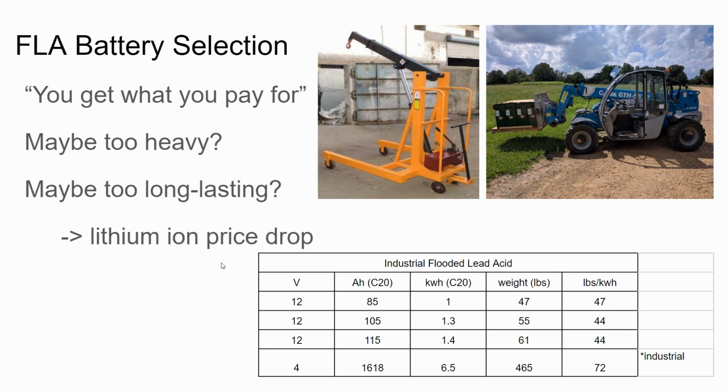So we're going to look at some of this, but generally you have to use what's called a battery crane. For the battery crane on this particular off-grid site, we had to rent a special forklift to get the things off the truck, because the lift gate of the truck was only rated for 3,000 pounds, and these things weighed 800 pounds each.